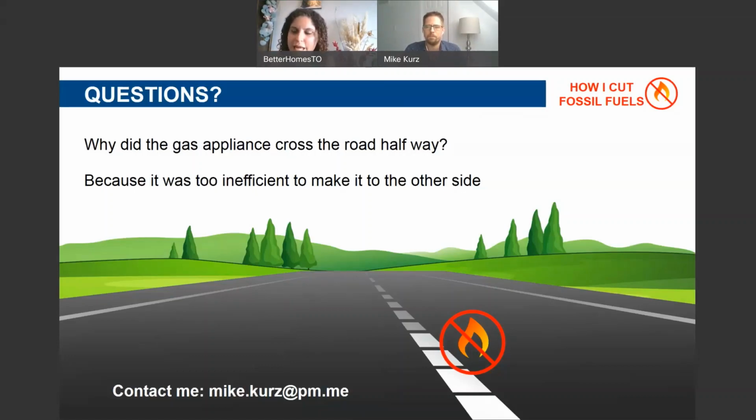Awesome. That's great. And then lastly, do you have any thoughts about the CO2 heat pumps? We did talk about that a little bit earlier, but any other thoughts? Yeah, they sound awesome. They can produce higher temperatures. They don't have high global warming potential refrigerants. Obviously, CO2 has a global warming potential of 1 versus around 2,000 for some of the other refrigerants, or even up to 4,000, I think. So I think that's definitely going to be coming up in the future. I'm hoping when this heat pump I got craps out that I'll be able to get a CO2 one next time.